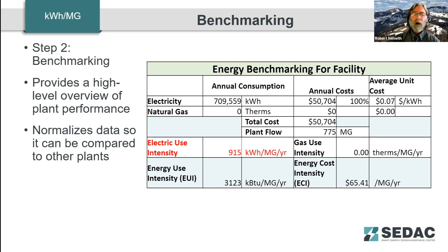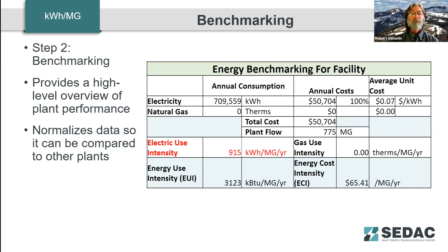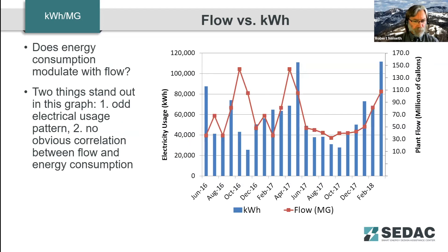Some plants use just electricity with no natural gas usage, but we'll sometimes have an additional column with monthly therm consumption. We take the flow and kilowatt hours and plot them on a chart. Two things kind of stand out here: there's an odd electrical usage pattern. You can see a high of over a hundred thousand and a low of 25,000 kilowatt hours. Sometimes these are easy to explain because they're billing errors from the utility; other times, they raise questions about what's going on at the plant.